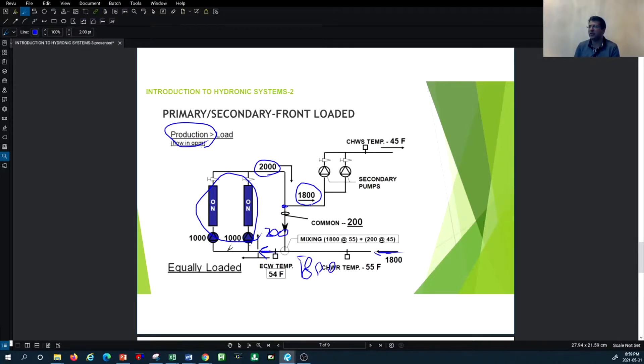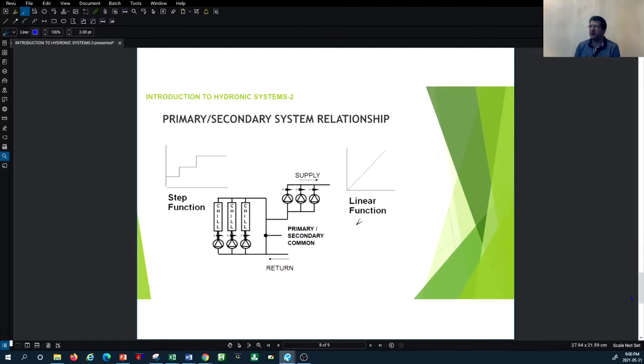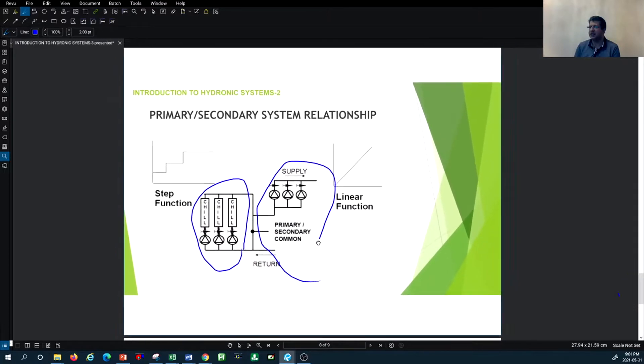At the mixing point, 55°F return chilled water mixes with 200 GPM of 45°F chilled water from the primary side. The resulting return temperature is colder than expected — we expected 55°F but receive colder chilled water return because primary production exceeds secondary demand. From a controls perspective, the functioning of the primary loop differs from the secondary loop, and we must account for this when managing the temperature and flow relationship.